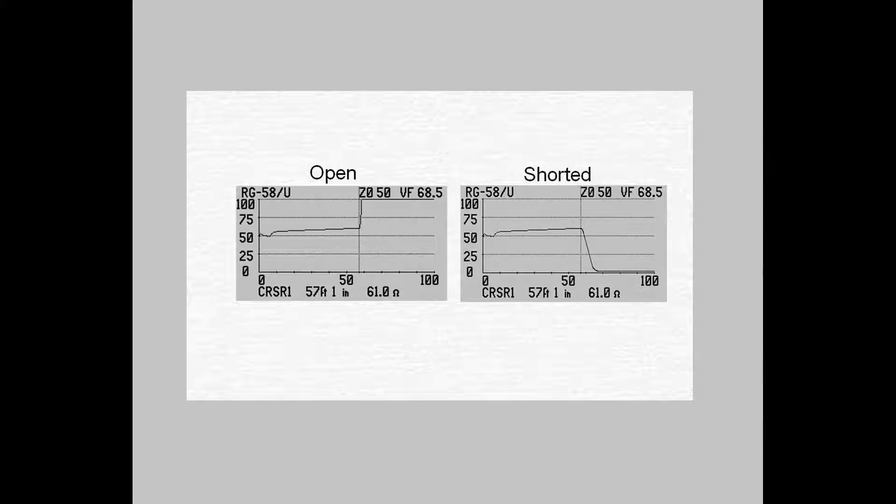The screen on the TDR will give you a graphical trace. It'll look something like this if you have an open, or something like this if you have a short. The actual problem is shown right here. Reading the scale on the bottom, you'll see that it's approximately 56 feet out from the end of the wire you're measuring. Later in this video, I'll go into greater detail on how to read this screen.